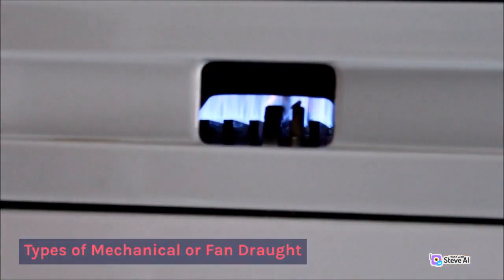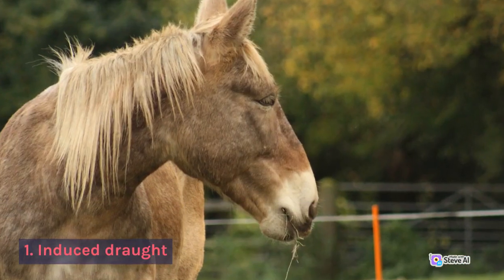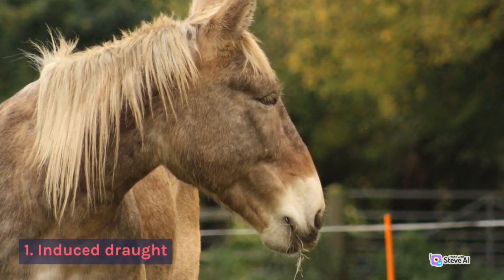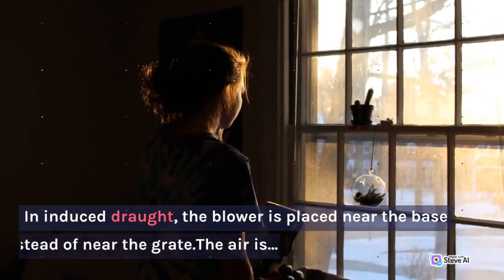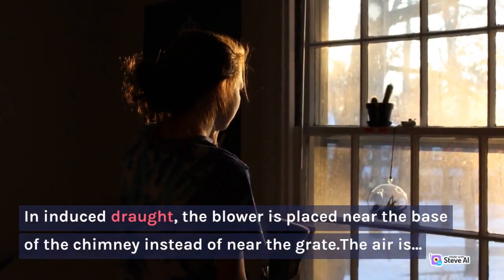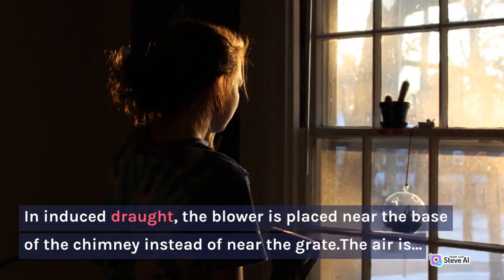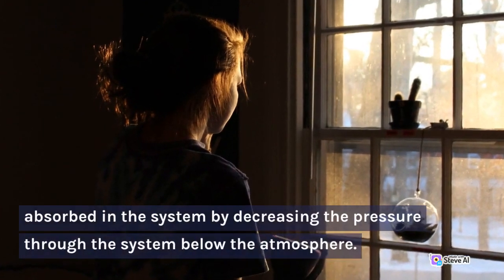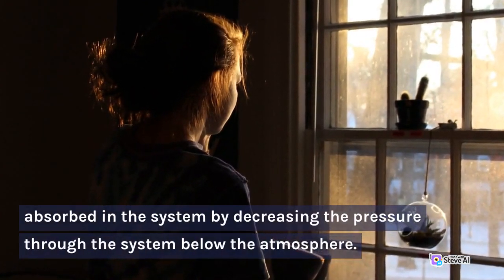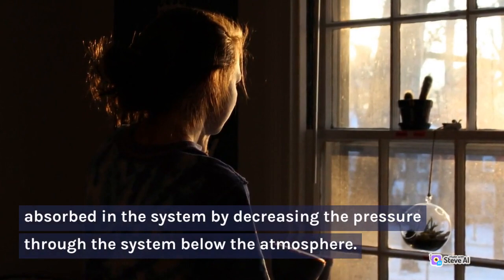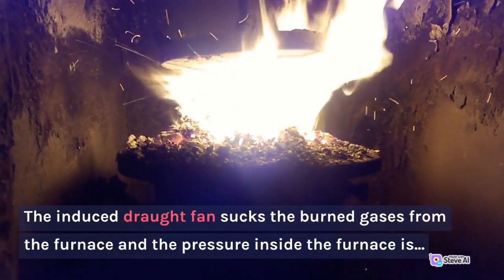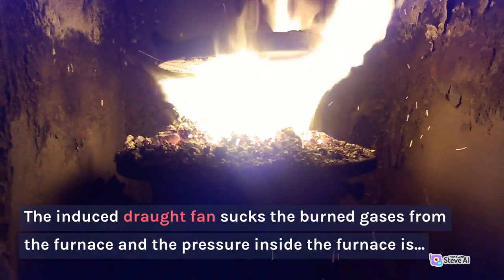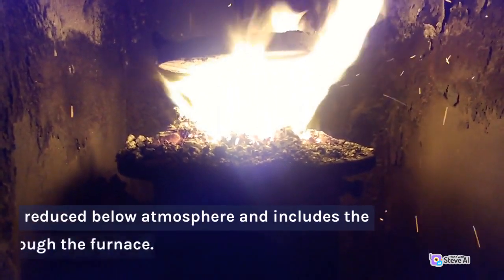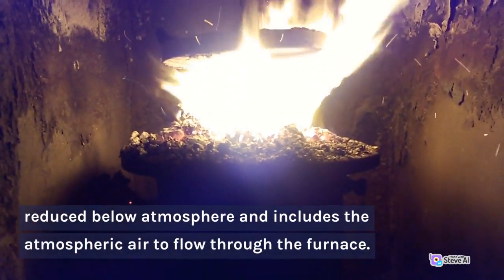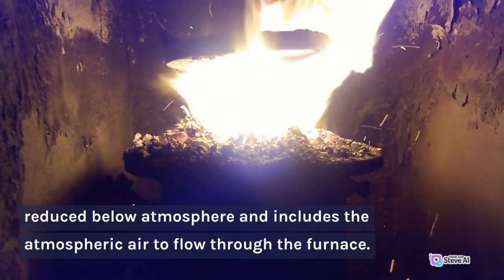Types of mechanical or fan draft. 1. Induced draft. In induced draft, the blower is placed near the base of the chimney instead of near the grate. The air is drawn into the system by decreasing the pressure through the system below the atmosphere. The induced draft fan sucks the burnt gases from the furnace and the pressure inside the furnace is reduced below atmosphere and induces the atmospheric air to flow through the furnace.